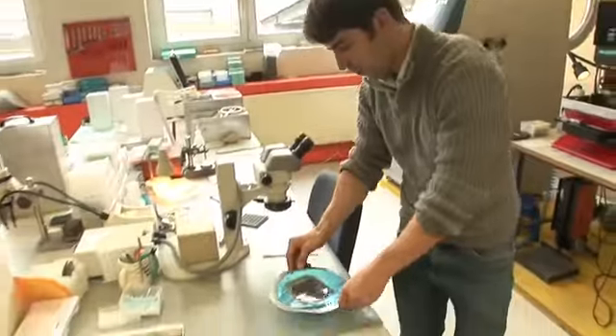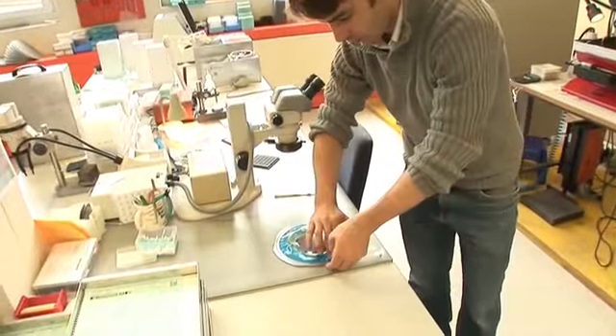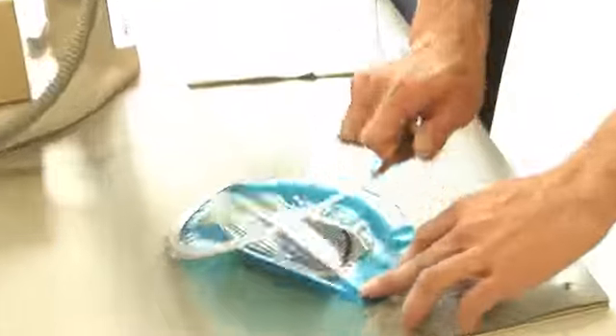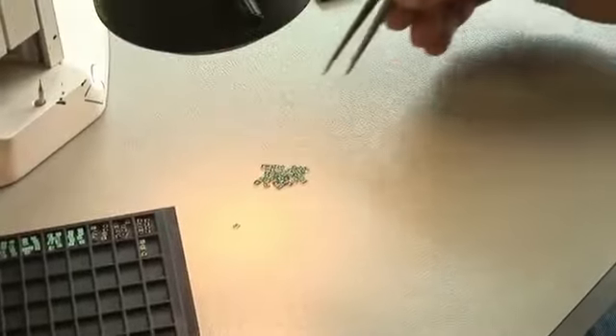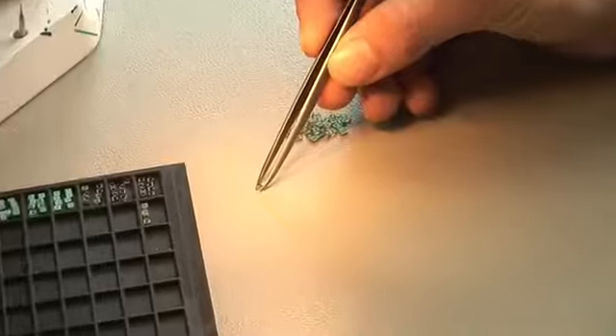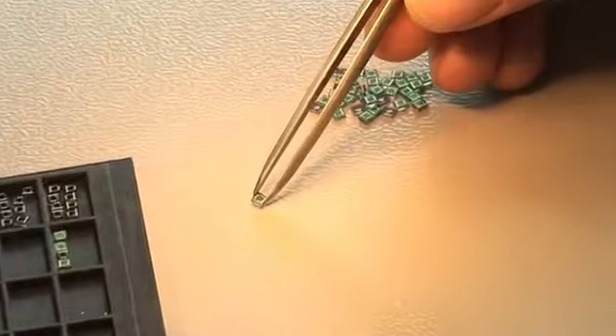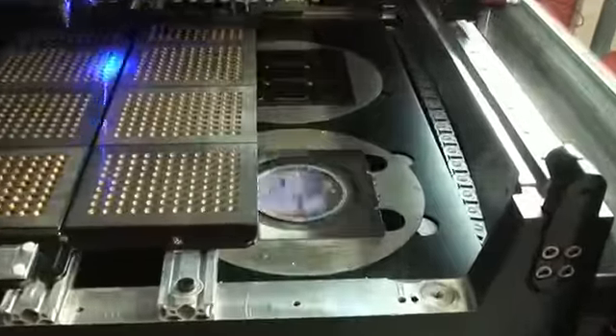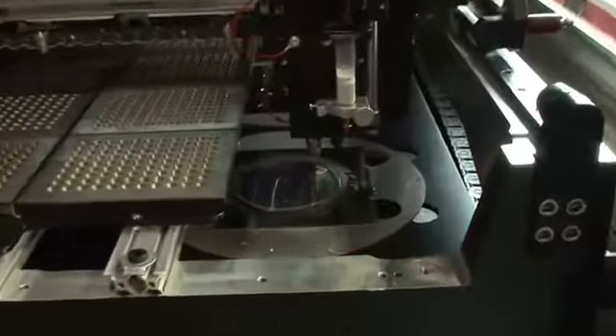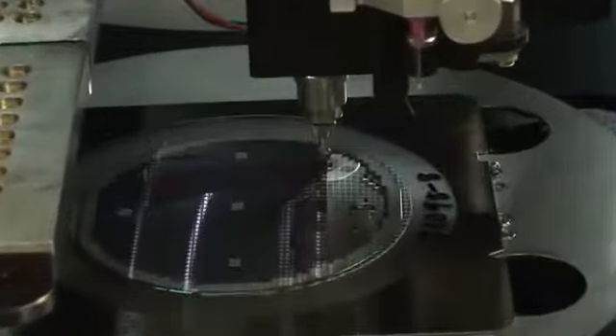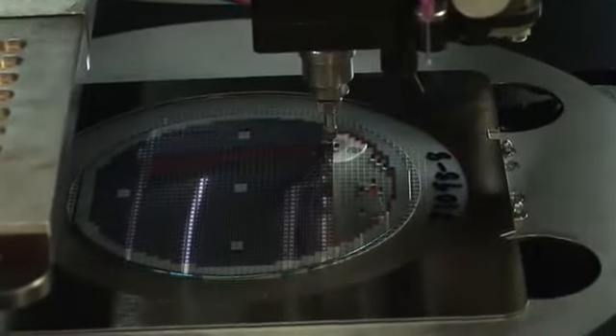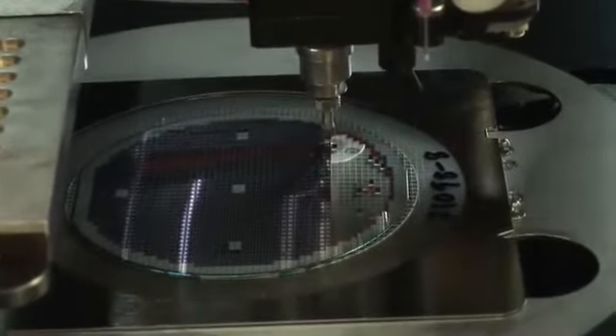In the next stage of production, after the sensor element's pressure range and reference point have been defined, the wafer is machine cut into individual pressure sensors. Each sensing element is fixed onto base plates, known as glass feed-throughs, for further processing. This is often done by bonding the sensor element to the glass feed-through. The adhesives used remain a well-kept trade secret.